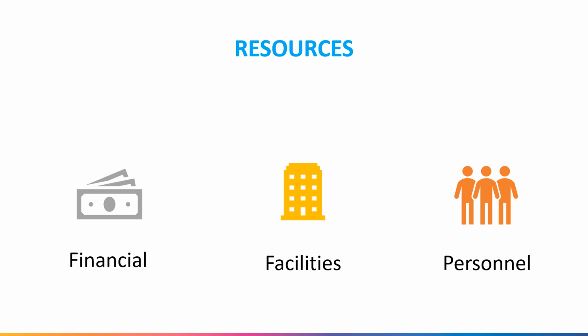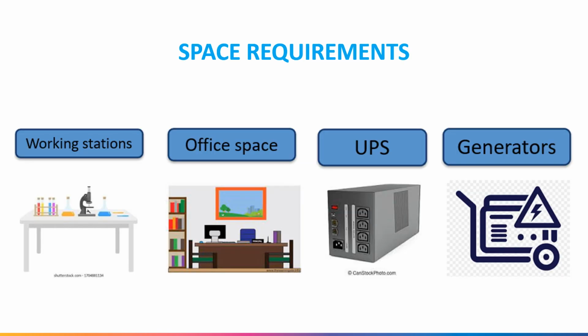As mentioned, facilities should be adequate depending on the lab processes. Some space requirement examples are: workstations should be spacious enough for work being performed, meet ergonomic standards, and be strong enough to hold equipment. An office space should be provided, which can also be considered as a clean area, meaning no samples or contaminated equipment allowed inside, for staff to do office and admin work related to the lab. UPS and generators are important as they are a backup power supply in case of power failure, and rooms requiring electrical supply should have UPS outlets installed.